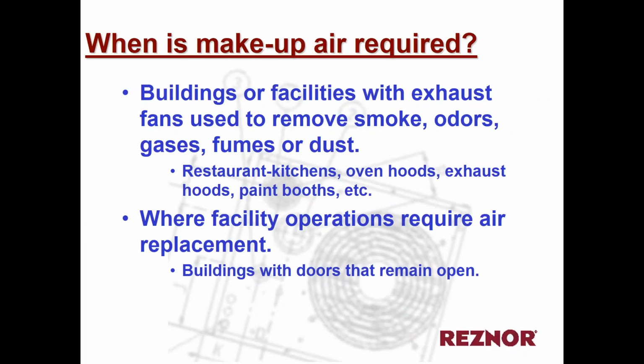So where would we use make-up air? Where would it be required? It would be required in buildings where exhaust fans are used to remove smoke or odors or fumes or dust, such as kitchens, oven hoods, paint booths, and things of that nature. Also in facilities where air is required for pressurization, where we want to slightly pressurize the building so that we can keep doors open, dock doors, or make it easy for doors to open when we're entering a space because of exhaust fans.